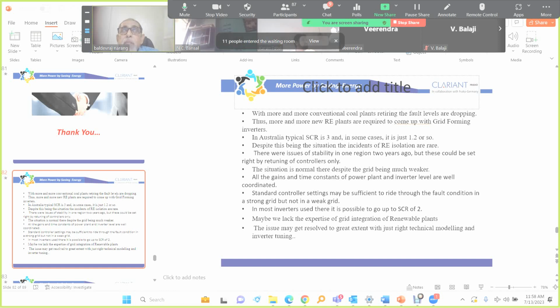And another question, sir: what is the response time -- 5 milliseconds, 10 milliseconds, or 20 milliseconds? Whether the WTGs and the inverters are capable of supporting the grid voltage within 5 or 10 milliseconds at the point of interconnection, when it is 100 kilometers away from the generator.